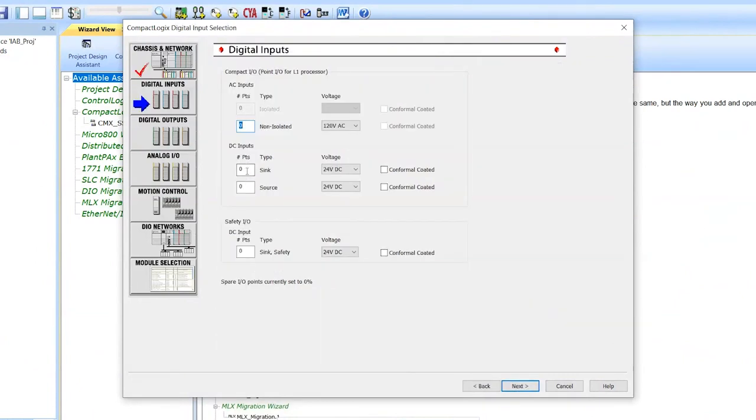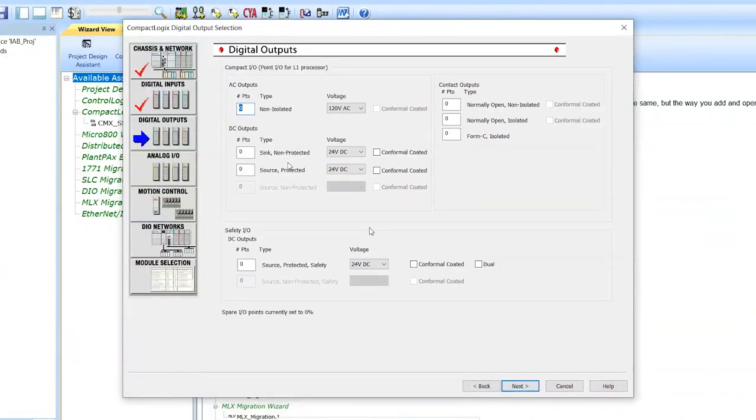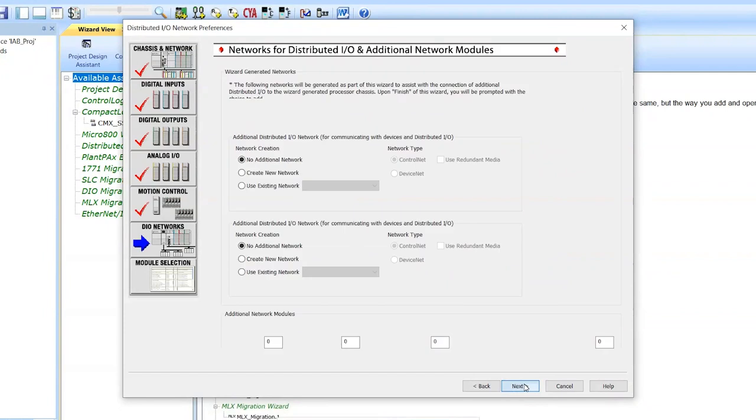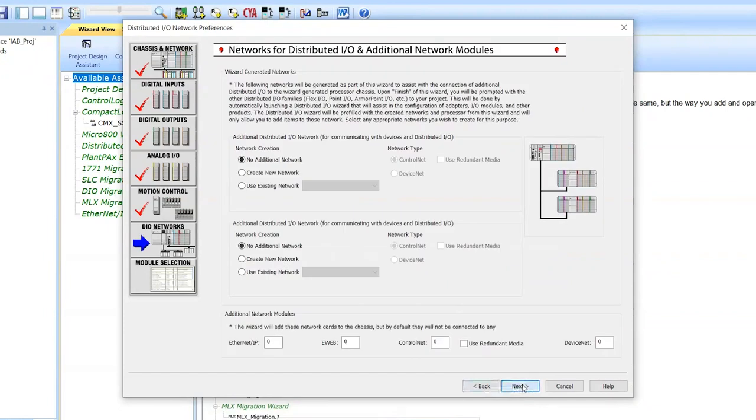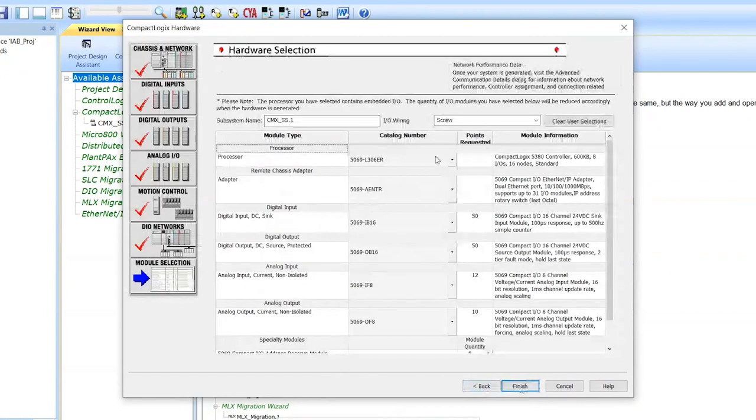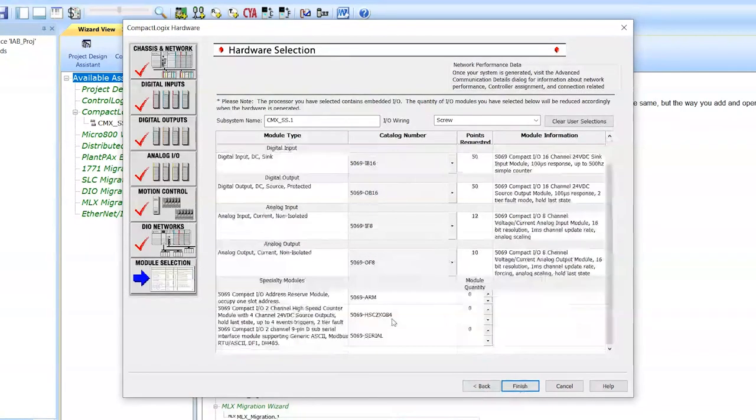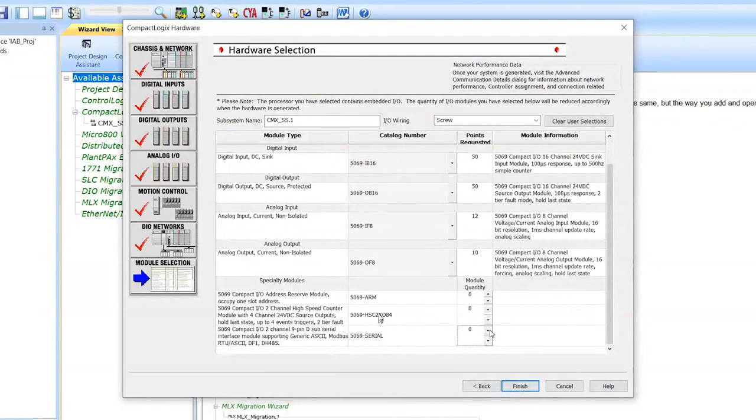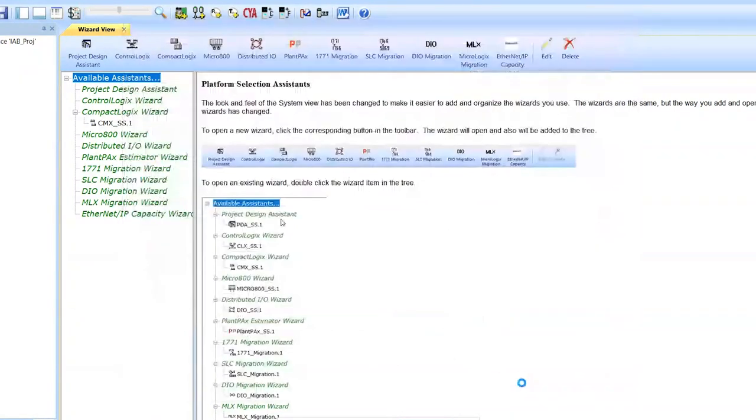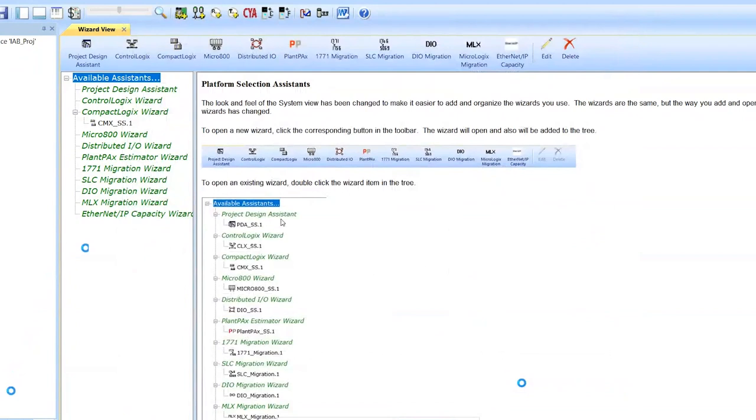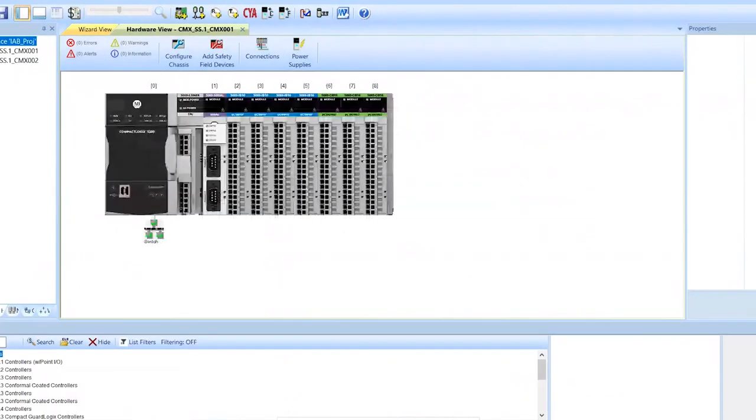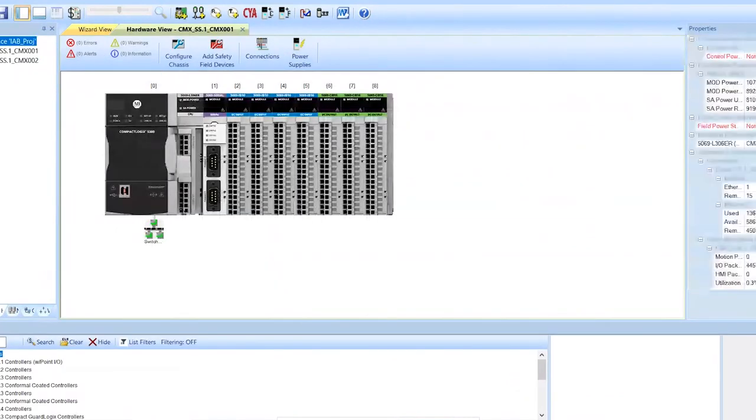And then all you do is type in your I/O count. If you've got, you might have 50 digital inputs, 50 outputs, and then you can do your analogs, throw a few numbers in here. You can add another network if you like. And then it gets you to the last page, what it would select, and it will also allow you to add some other things if you need a serial module or a high-speed counter. So we can add a serial module and then finish. And what that does is it builds your system for you.